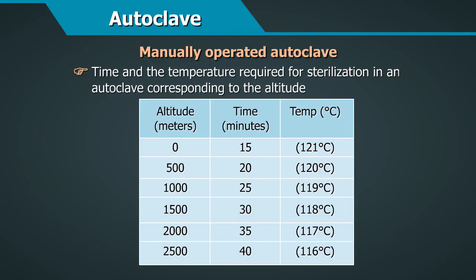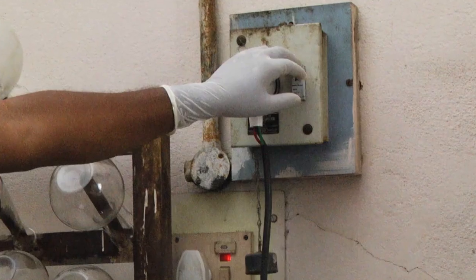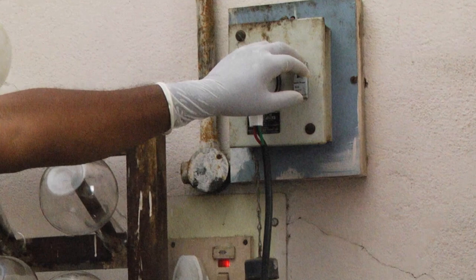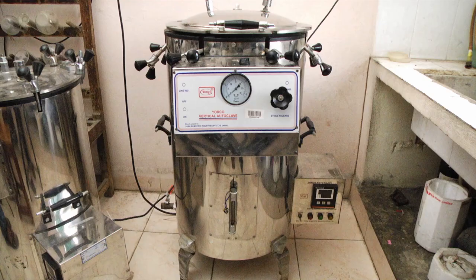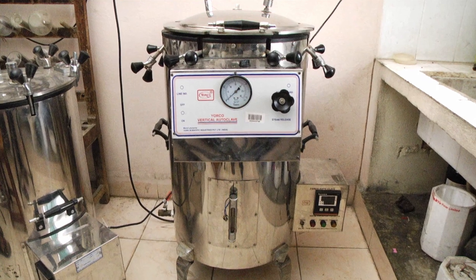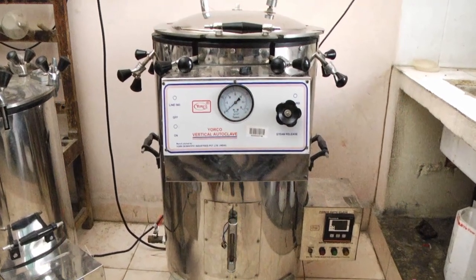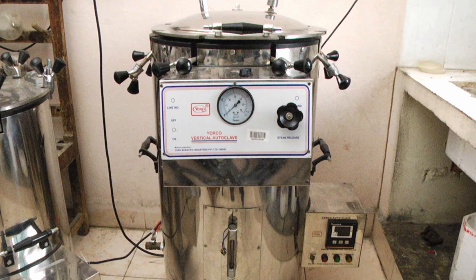Depending on altitude, set the timer. This chart gives the time and the temperature required for sterilization in an autoclave corresponding to the altitude. At the end of sterilizing time, turn off the heat and allow the autoclave to cool naturally. This will usually take several hours, particularly for agar culture media, to cool sufficiently for safe handling.